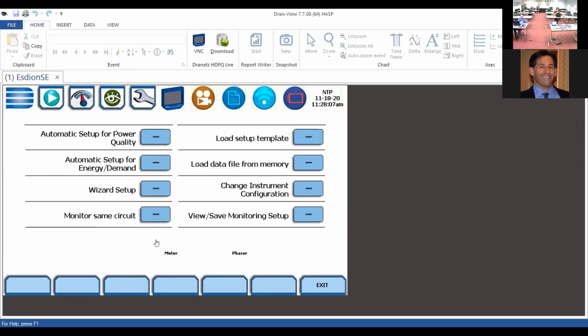And if I select it, then you see you have your different functions here: automatic setup for power quality, automatic setup for energy demand. Again, that sort of demonstrates the versatility of this particular product, where I can use it for virtually any power monitoring application. So it's not just power quality, it's not just energy demand, it can be both. So it's the most versatile instrument on the market as far as monitoring power. I like to use power as opposed to power quality. When you say power quality, it kind of puts it into this niche of power quality only. You may have an application in which you need to do a demand survey or things of that nature, and this instrument is equally capable of doing that. But having said that, our application here is going to be set up for power quality. And really, it's just a couple steps. You would select this option.